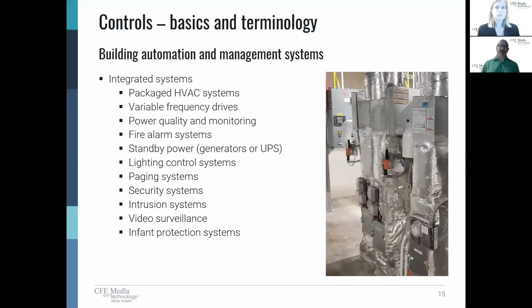It's very common for us to use the building automation system to perform other functions. I'm really interested, for example, from a lighting standpoint, to give the facility the ability to control lighting sequences or turn lighting on or off or control programming of lighting through the building automation system. You can also gain status of other systems that aren't mechanical. If you would like your technicians to get a text message every time the generator starts, the building automation system is probably going to be your best way to do that. So we're going to have to coordinate, though, during design between all the various engineers, electrical, technology, et cetera, and the mechanical engineers of how many points we need, because we're going to have to gather that data and call that out on the diagrams.